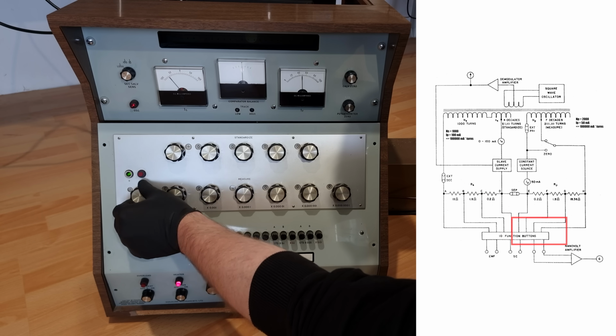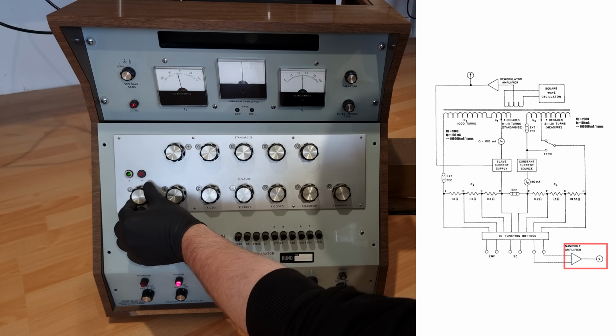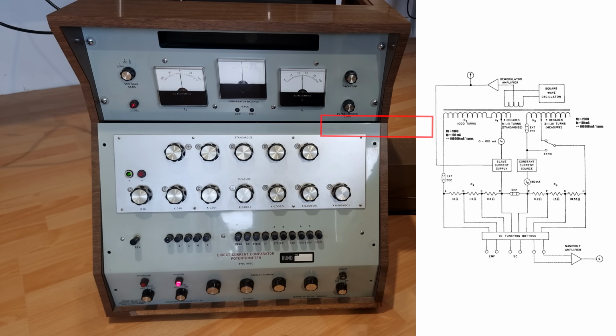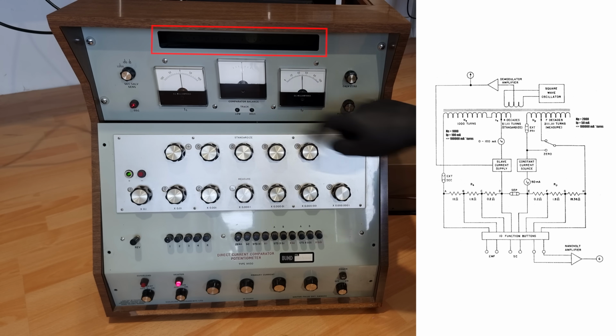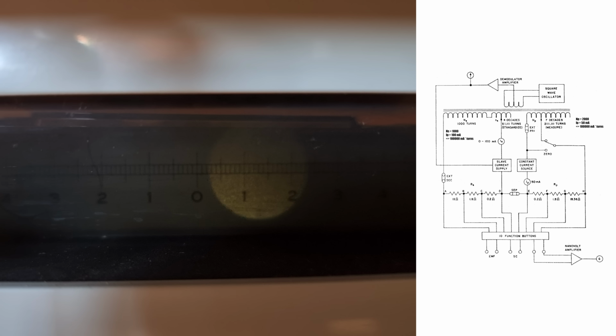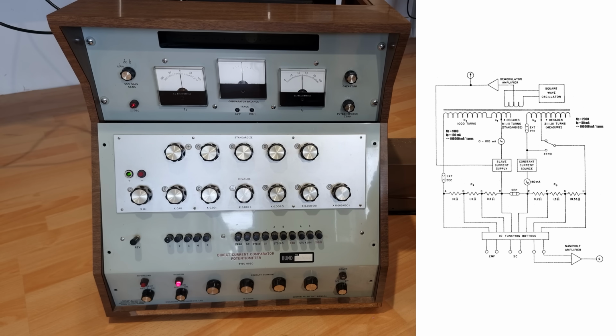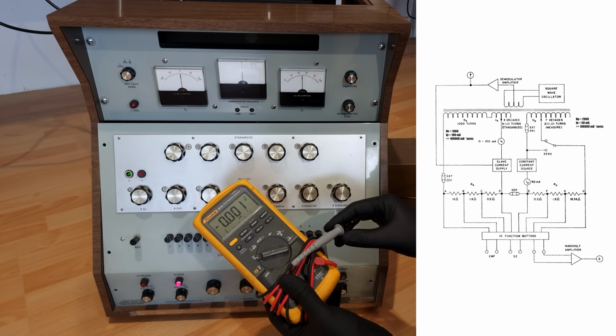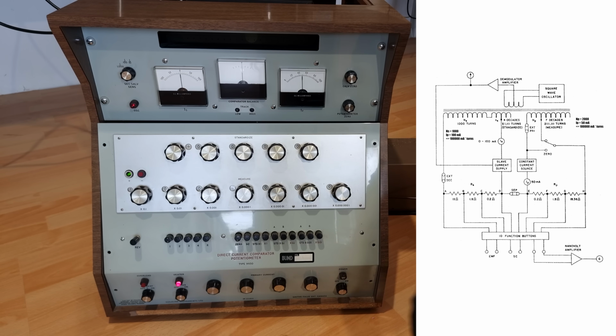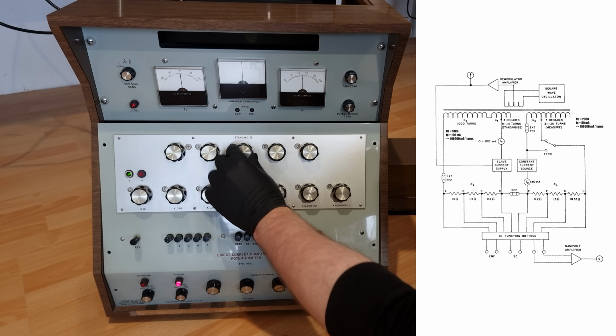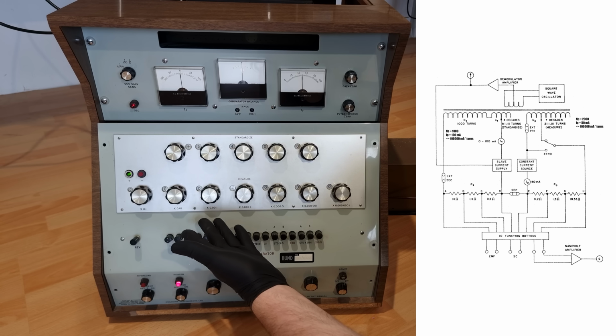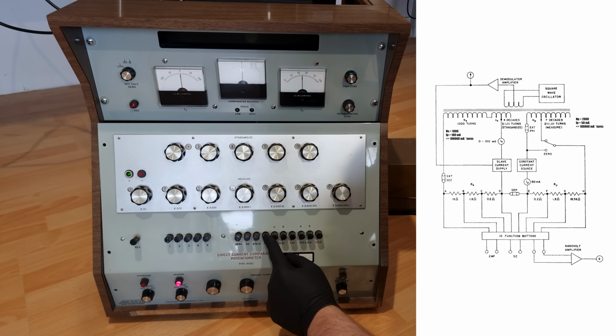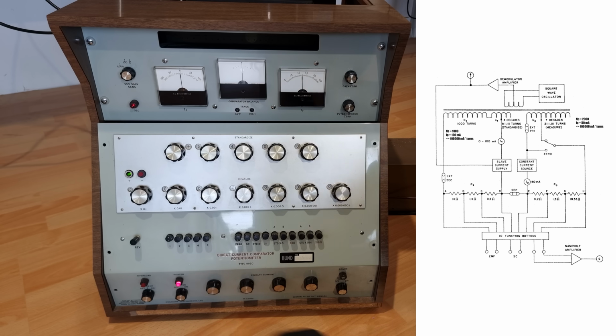That generates a voltage. And finally, the purpose of the Nanovolt amplifier and this upper light beam galvanometer is to find out exactly when that voltage and whatever we wanted to measure are equal. Yeah, putting it like that, it may sound a bit crazy in comparison to just taking a DMM measurement. But again, a DMM measurement depends on countless non-ideal components and their interactions. Whereas this can be standardized to a voltage standard. And then we can make arbitrary voltage measurements approaching perfect linearity, depending only on a constant current source, one resistor, and eternally stable comparator winding ratios.